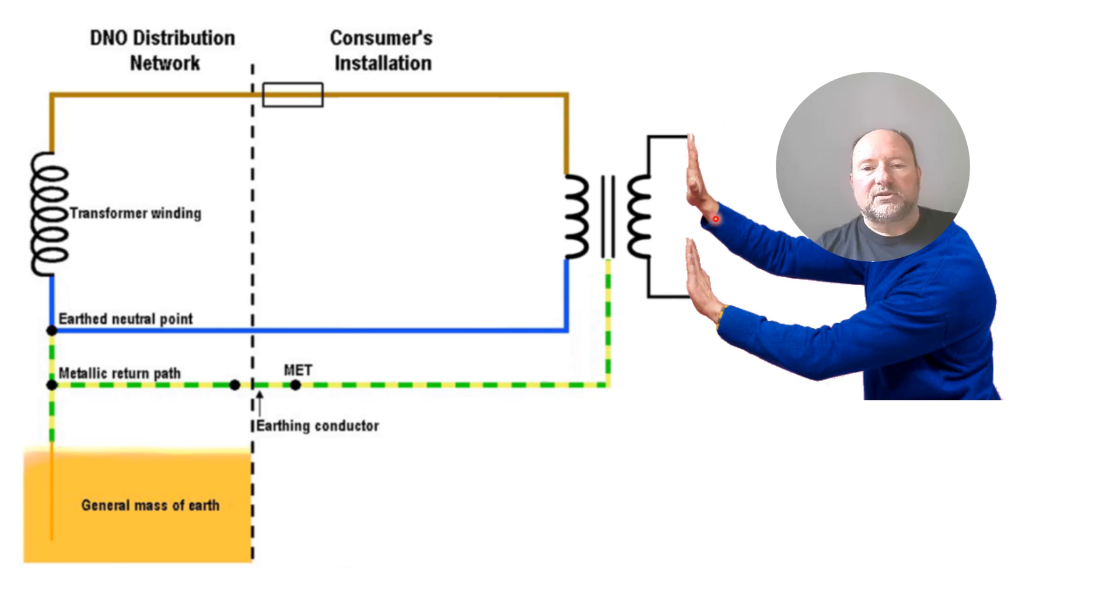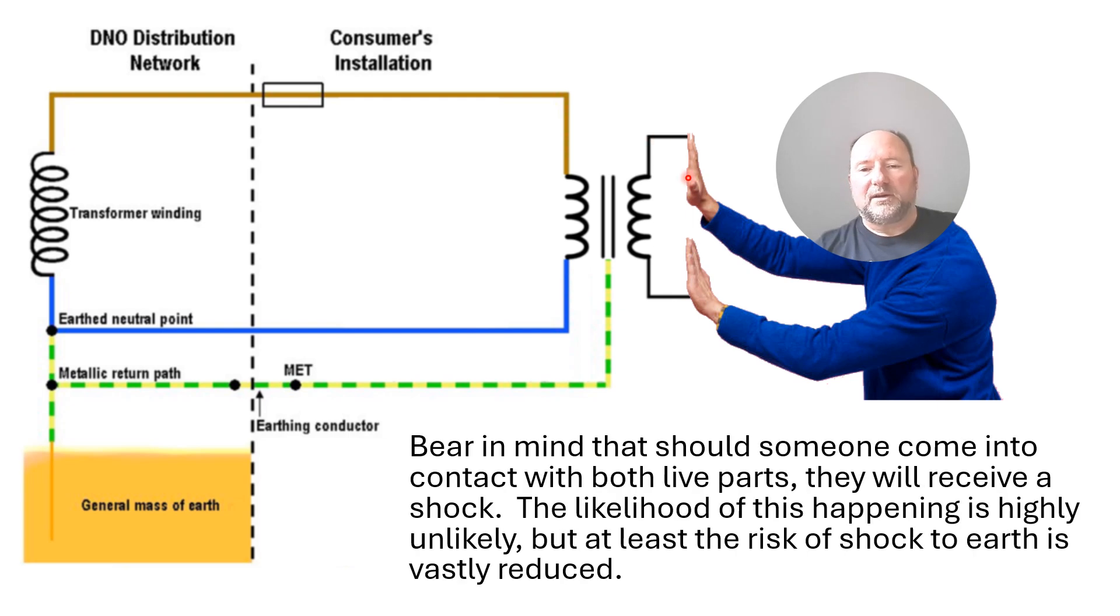Now, make no mistake that if you were to come into contact with both these live parts, you'll get a shock because certainly in the case of a shaver point transformer, there's still 230 volts across these two points. So the shock will take a path down the arm across the chest, affecting the heart and the breathing, back up the other arm and back to this point. So that is the path the current will take should you come into contact with both the live parts.